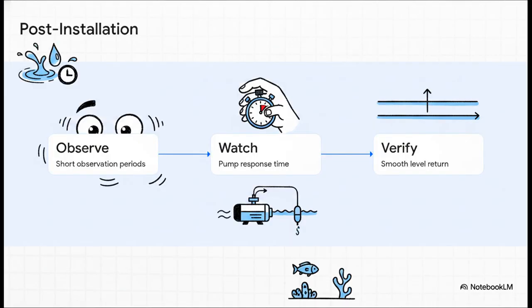Also, right after you install this whole shebang, don't just walk away. Follow these vital best practices. Start with short observation periods. Actually stand there and watch how quickly the pump responds when the water level drops. Verify that the tank returns to the exact intended level smoothly without overshooting. Doing this helps you catch an incorrect sensor placement or overly aggressive flow early on, way before it causes a problem while you're asleep.